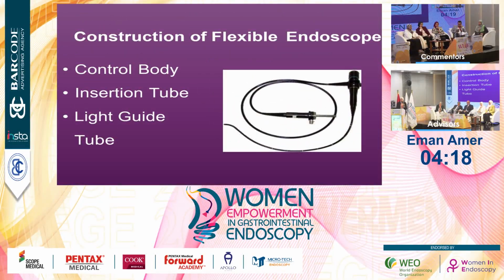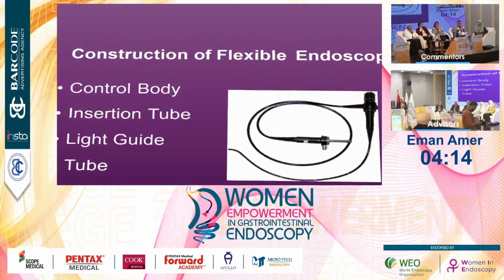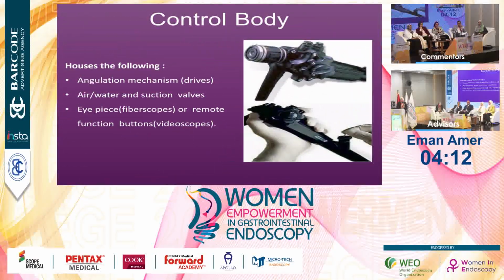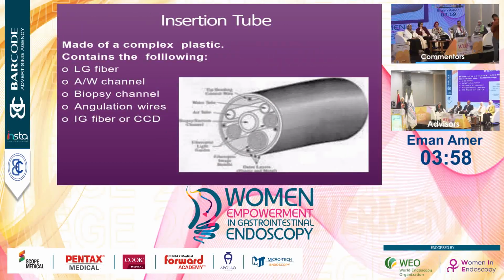Construction of the flexible endoscope: the control body, insertion tube, and light guide tube. The control body houses the following: angulation mechanism, air and water suction valves, eyepiece for the fiber optics, or remote function buttons for the video scopes. You see this small insertion tube is made of a complex plastic containing LG fibers, air and water channels, biopsy channel, angulation wires, and IG fiber or CCD.